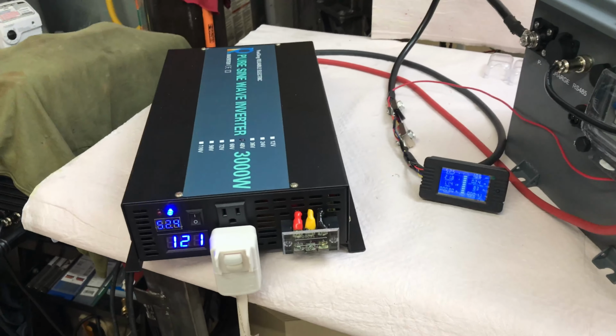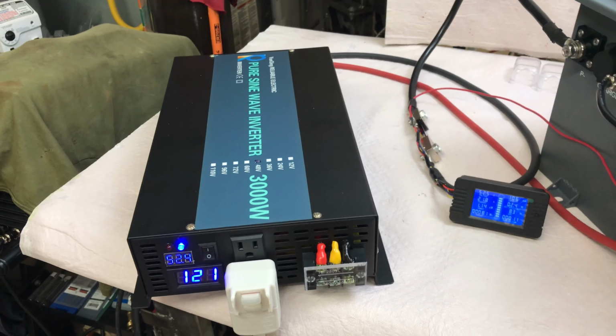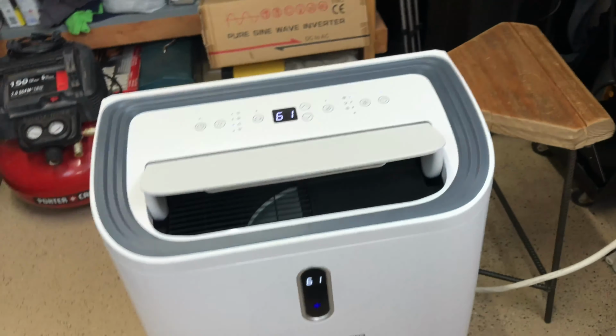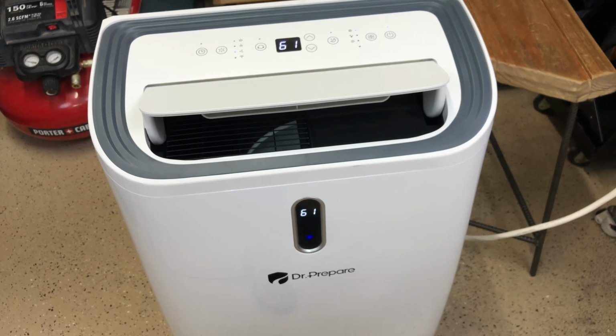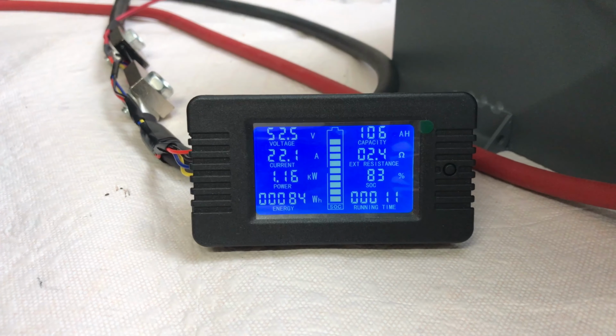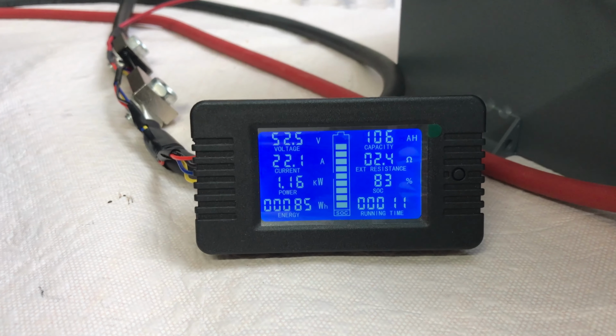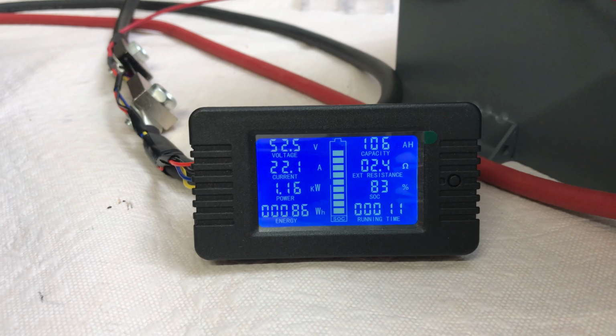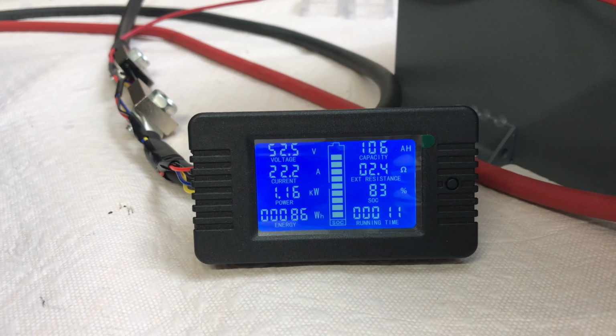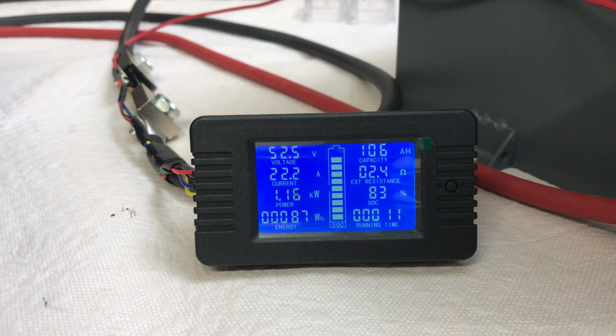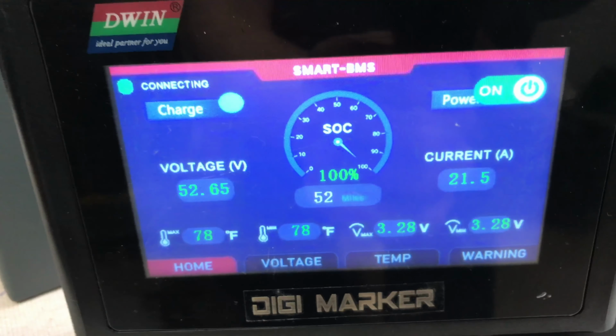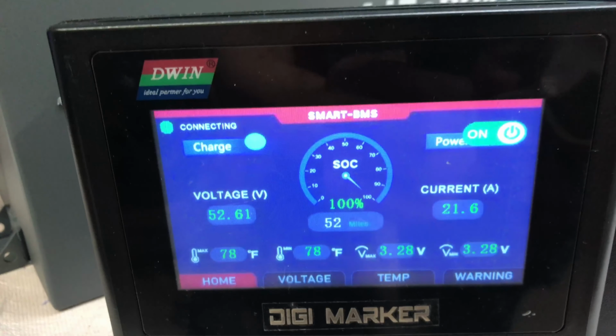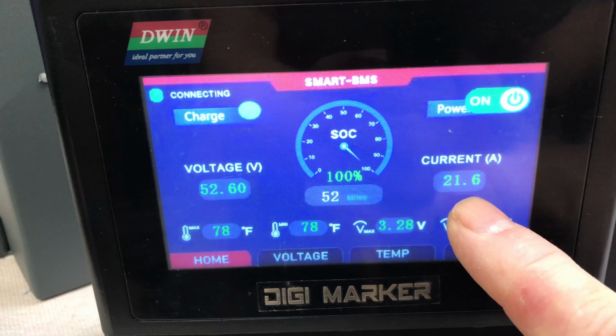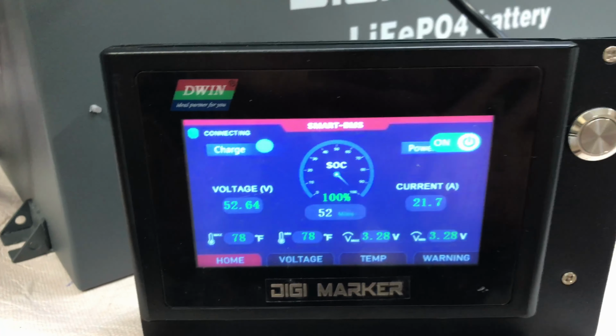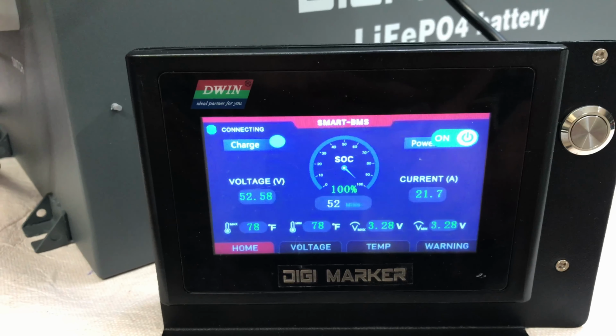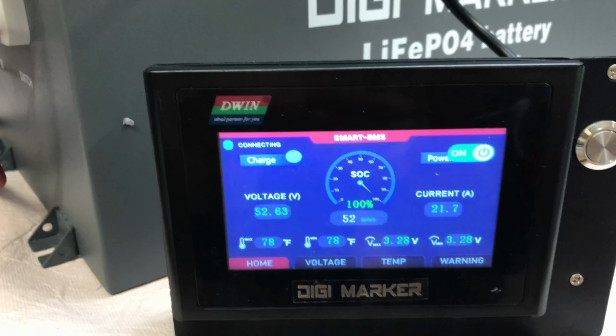Alright, we're all set up. I've got a 3000 watt 48 volt inverter running a 15,000 BTU portable AC unit, and the shunt meter all zeroed out. I just started the test, so we're pulling 22 amps. That'll fluctuate a little as the AC cycles on and off. The screen shows we're pulling 21.6 amps out of the battery right now, and we're at 100%, 52.6 volts under the load.